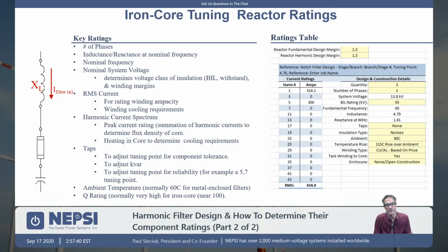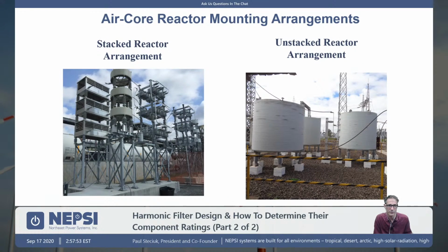But in the end, you're not looking to specify or to have a harmonic filter system that is running hot, that runs noisy, or that is unreliable. So this is what we typically would give to our suppliers. Just a couple pictures, air core reactors.